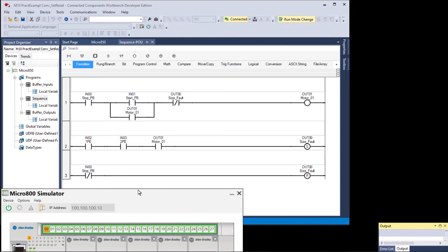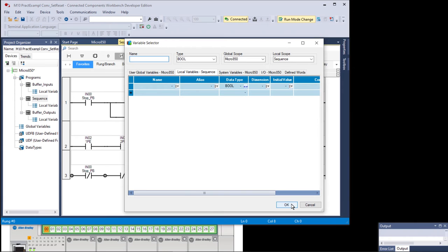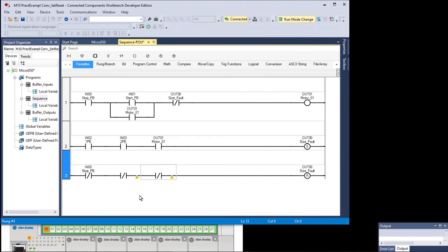So what you're looking at is a copy of the program. You're going to edit a graphical representation of what's in the controller. Then when you accept your changes, after you test them, it's going to replace the program that's running in the controller with the one that you're editing right now. So our whole reason for going aside here on this rabbit trail was to say that we don't want them to be able to reset it unless 1PE, 2PE are clear. You always are taking a chance when you do this live in front of a group of students if you go off with some brilliant idea.